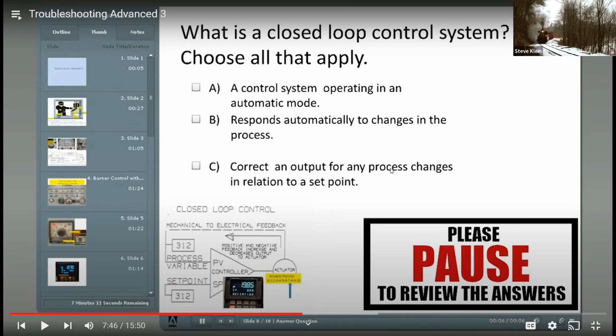It's like A and C. Same on your asphalt - I can set the asphalt wherever I want to in manual, but if the tonnage changes, it's wrong. If I put it in automatic, the signal that it's sending back in as to how much the flow is will be automatically controlled and proportioned. That is a closed loop system - you make a change, an answer comes back in, and then depending what the answer is, the next change is made.